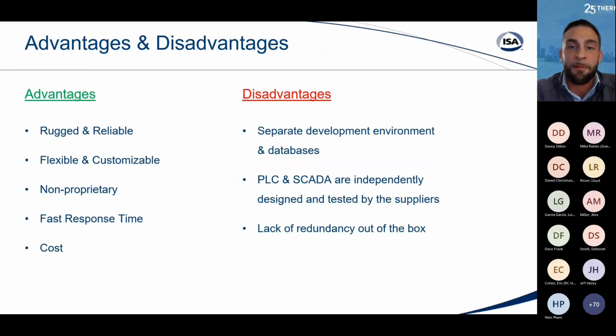Lastly, to round out my part of the presentation, I want to talk about the disadvantages and advantages, starting with advantages. PLC SCADA systems are rugged and reliable, talking about the PLC hardware, which is designed to withstand high vibration, high temperature, and high humidity environments, and generally has a very high mean time to failure. For the SCADA hardware—more computers—depending on the grade, if it's more industrial grade, you can keep it in a suitable environment, but generally you want to keep computers in a controlled environment.